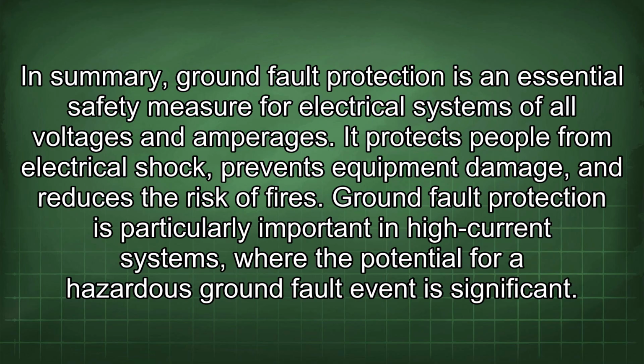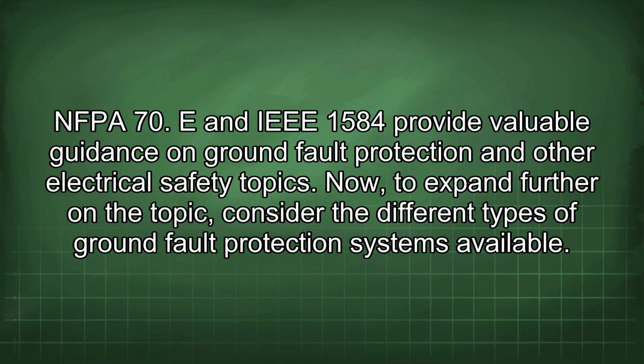In summary, ground fault protection is an essential safety measure for electrical systems of all voltages and amperages. It protects people from electrical shock, prevents equipment damage, and reduces the risk of fires. Ground fault protection is particularly important in high current systems, where the potential for a hazardous ground fault event is significant. NFPA 70E and IEEE 1584 provide valuable guidance on ground fault protection and other electrical safety topics.